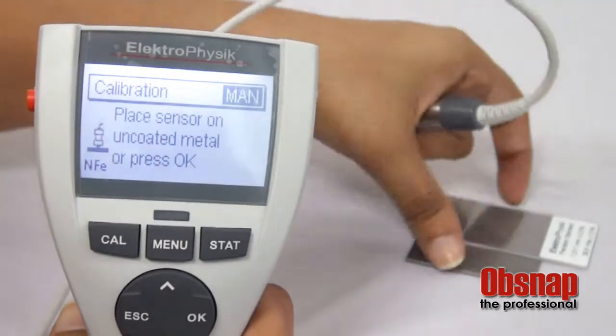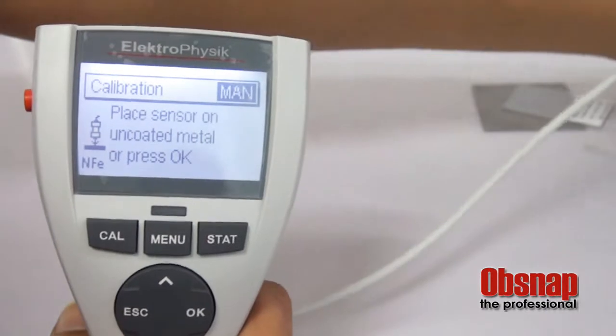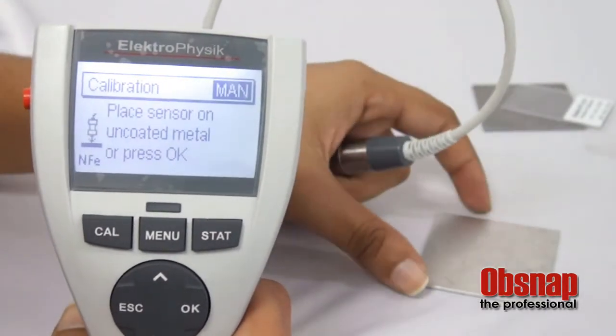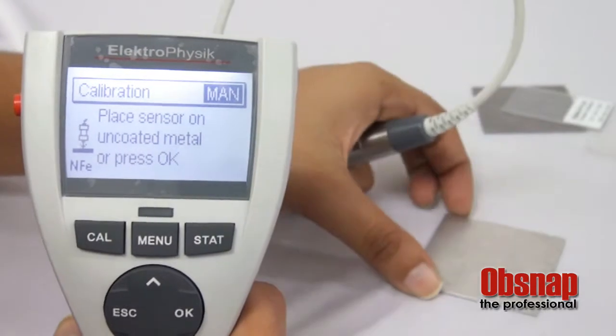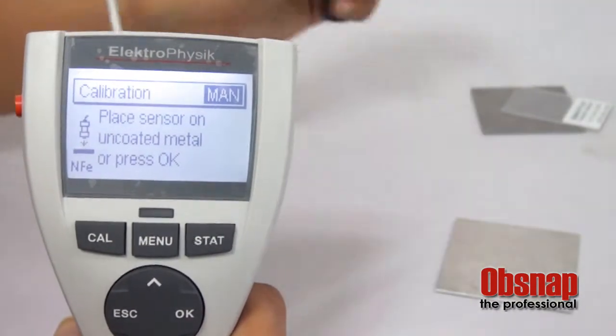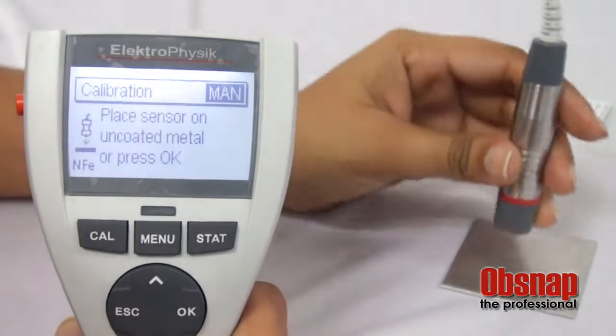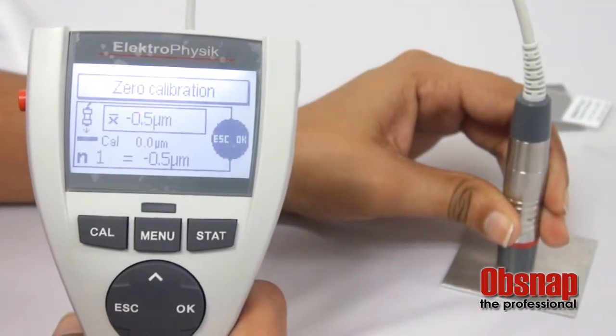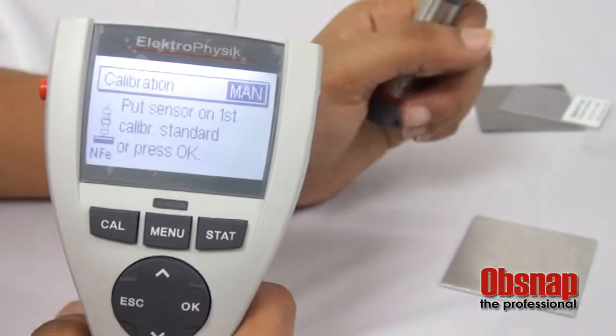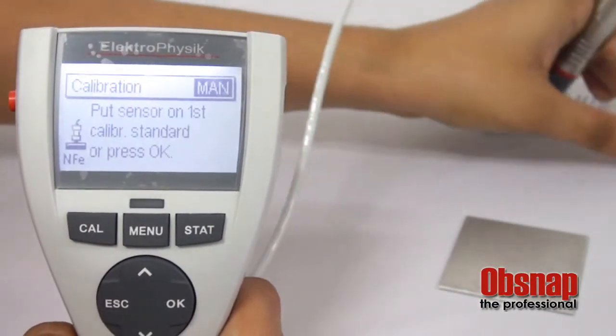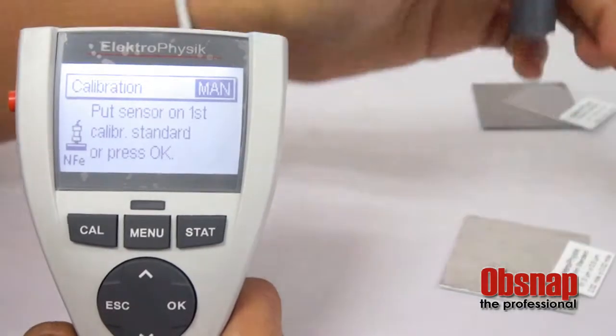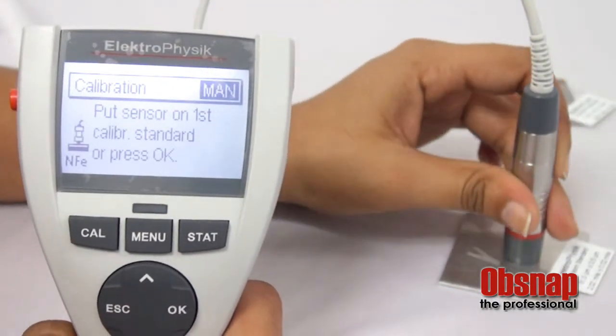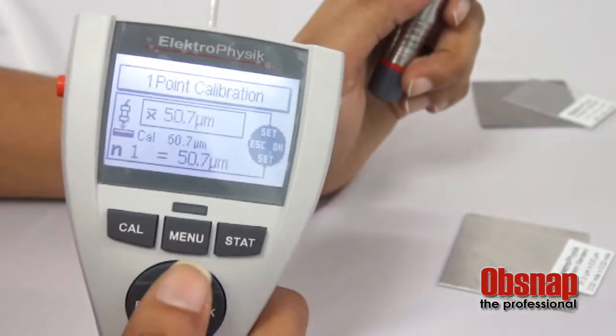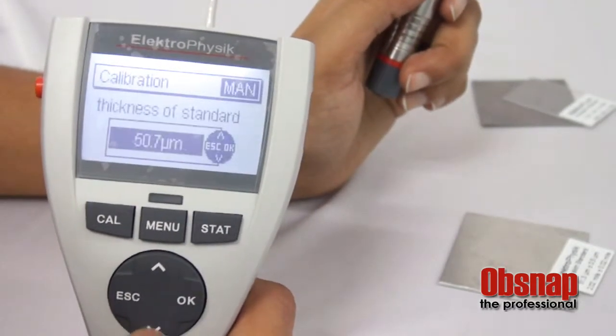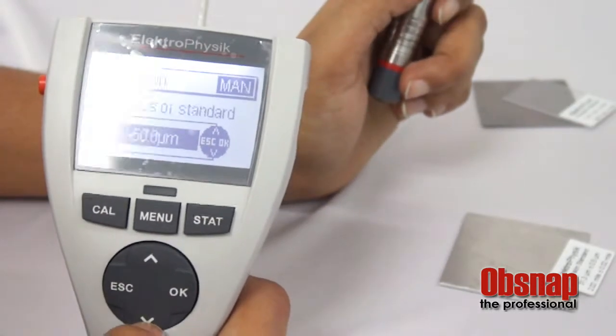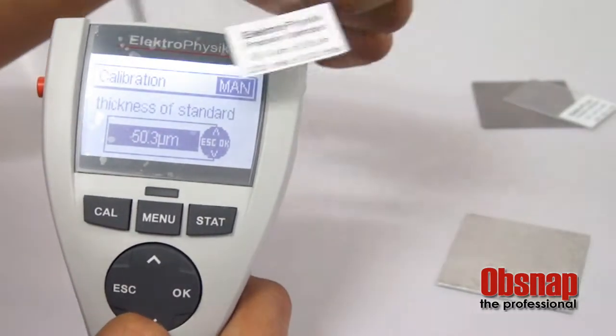Now put the sensor on this uncoated, put the sensor on the non-ferrous plate. On this non-ferrous plate, you can start measure on zero plate, then click OK, then put the sensor on the first standard calibration foil. Adjust the reading according to your setting, according to the standard foil reading.